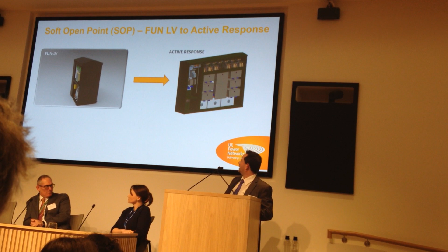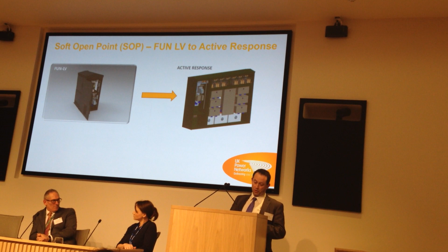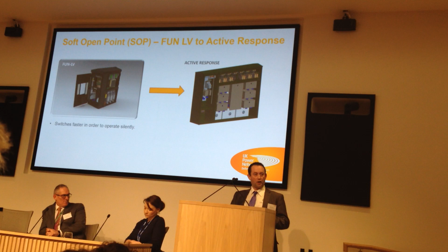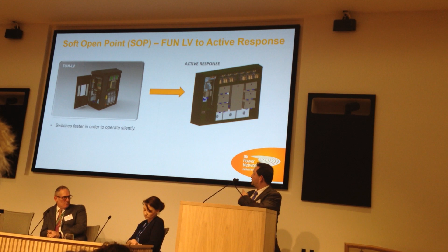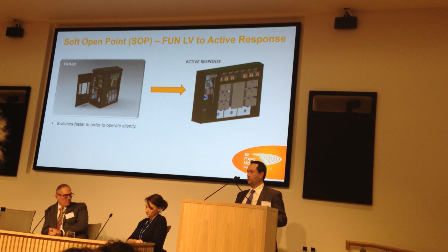Hence Active Response picks the project up from this point. What you can see here is the second generation of the SOP we're developing for Active Response. The key difference is the device on the right switches a lot quicker than the device on the left. That solves a couple of issues. First of all, if you switch at 5 kHz like we did on FUN-LV, you can hear it, you get a whine. If you switch at 20 kHz like we're doing on the system on the right, it becomes inaudible to us anyway - we may have a few dogs howling, but human beings should be okay. So we can switch faster, and it's a lot more quiet.